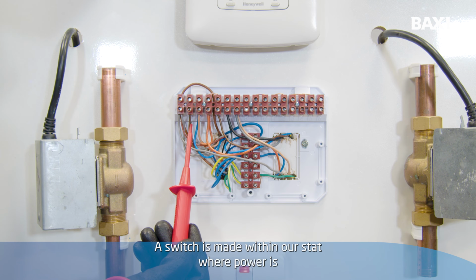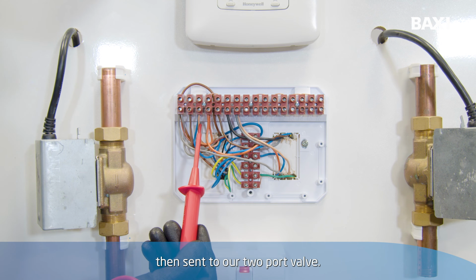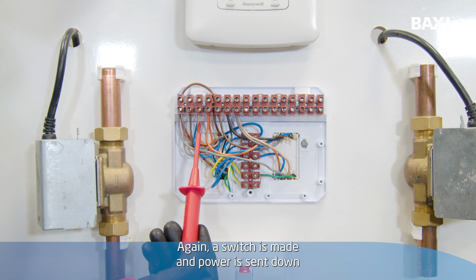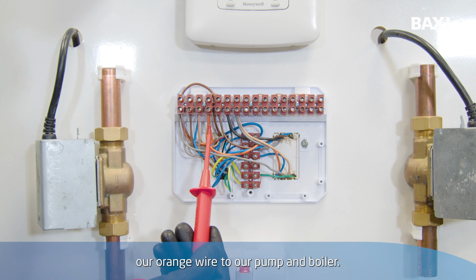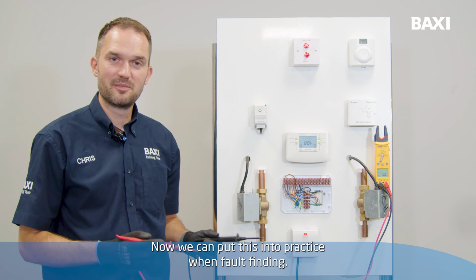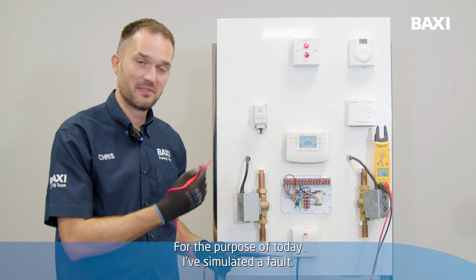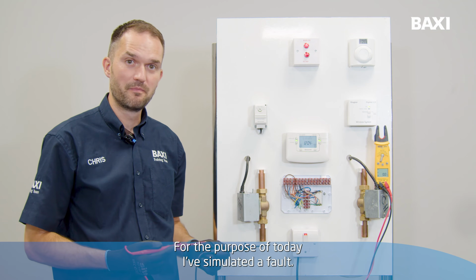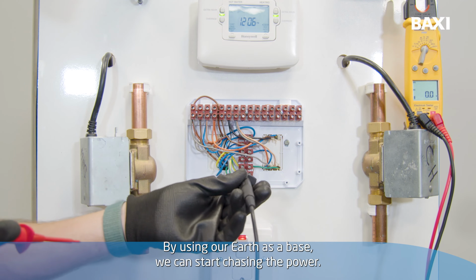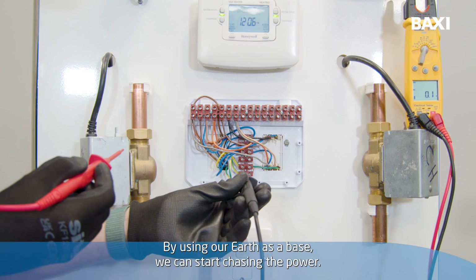A switch is made within our stat, where power is then sent to our 2-port valve. Again, a switch is made and power is sent down our orange wire to our pump and boiler. Now we can put this into practice when fault finding. For the purpose of today, I've simulated a fault. By using our earth as a base, we can start chasing the power.